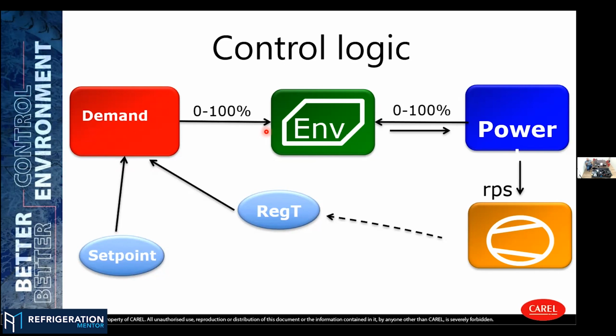So basically, we will take a look and see if the compressor is running under the envelope, as we discussed, or out of the envelope. In the case that we are out of the envelope, we will apply some offsets and some filters in order to force the system going back to the envelope. So it could occur that you have like 100% request from the field, and your compressor is running at 80 or 70% of full speed, mainly because it could be related to some protections that our controller is applying to the system. And then this information is transferred to the inverter, and the inverter will drive the compressor.